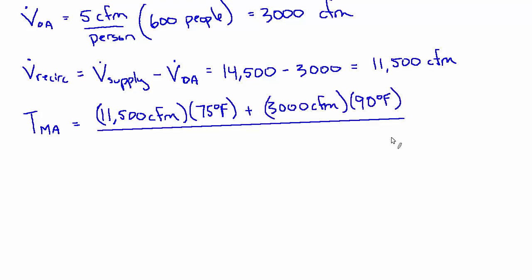divided by the total CFM, 14,500, and that equals 78.1 degrees. That's the mixed air temperature, and that's the temperature of the air that's entering the coil. So that is another one of the answers that we need.